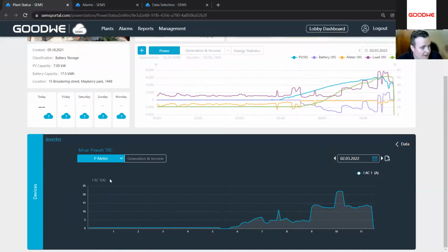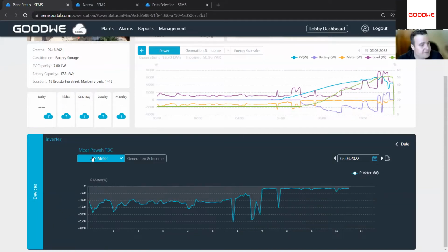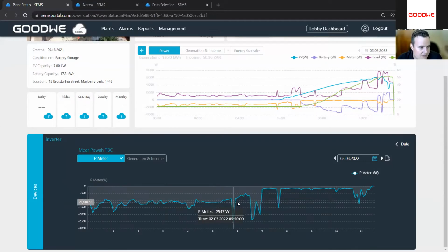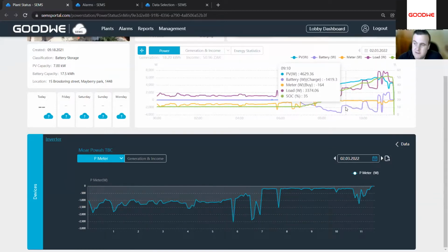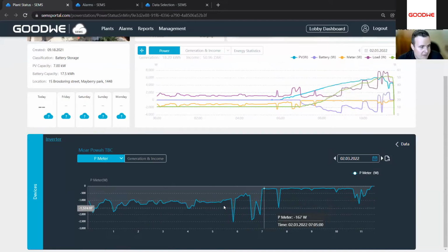Especially when we're installing, we want to see that our power meter and everything's installed correctly. When we have issues with the smart meters or wiring of the smart meters, especially on the 3-phase, I use the power meter quite frequently. On the 3-phase devices in this drop-down list, way at the bottom, you'll find phase 1, phase 2, phase 3 of the smart meter. I'll show you an example of how and where I've seen problems like this in the past. So yeah, with our smart meter, we can see it's all consumption from the utility. There's no export. This plant does not allow export to the utility. So should this all have been flipped and we see during the night, we just see export, then we know there's a problem with the smart meter.